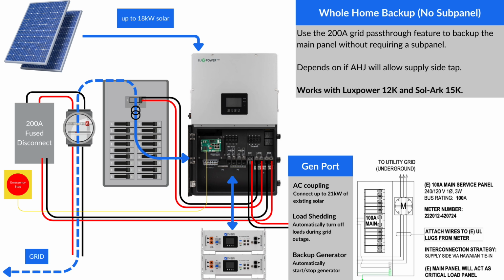These inverters have the capability and functionality to allow up to 200 amps to pass through, and if a grid outage does happen, then this will isolate the main panel and allow those circuits to continue to be powered. This can really help when it comes to reducing installation time and cost, as well as helping to avoid more panels, more items on the wall.